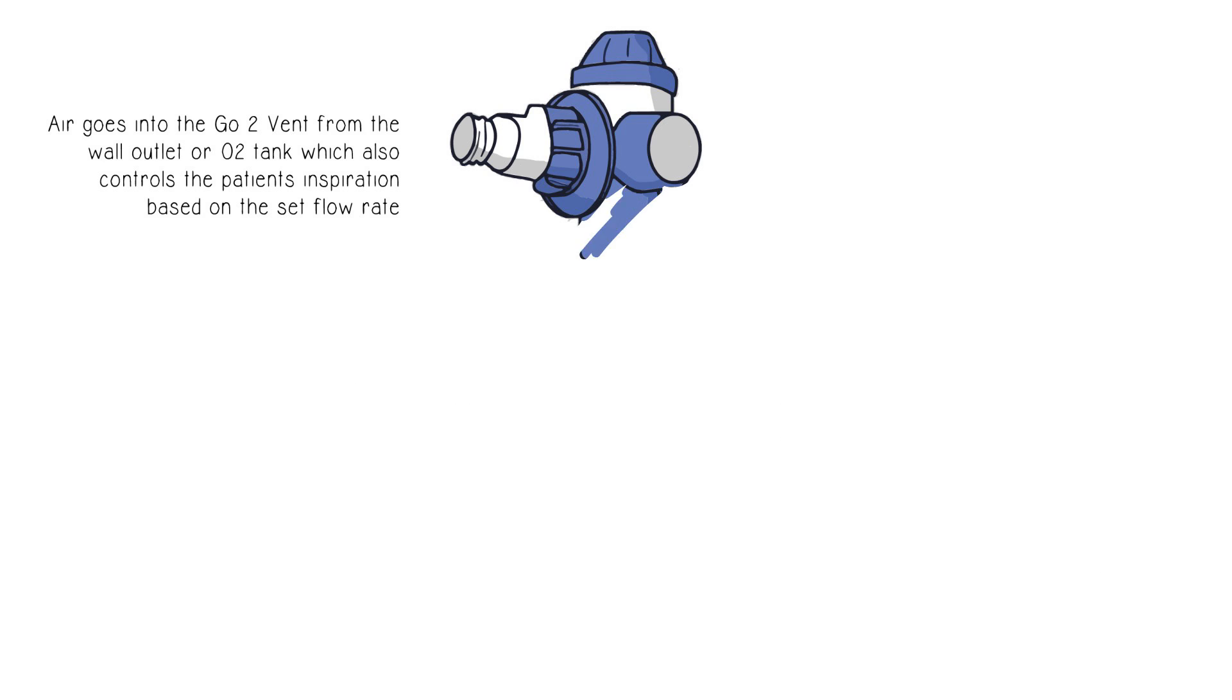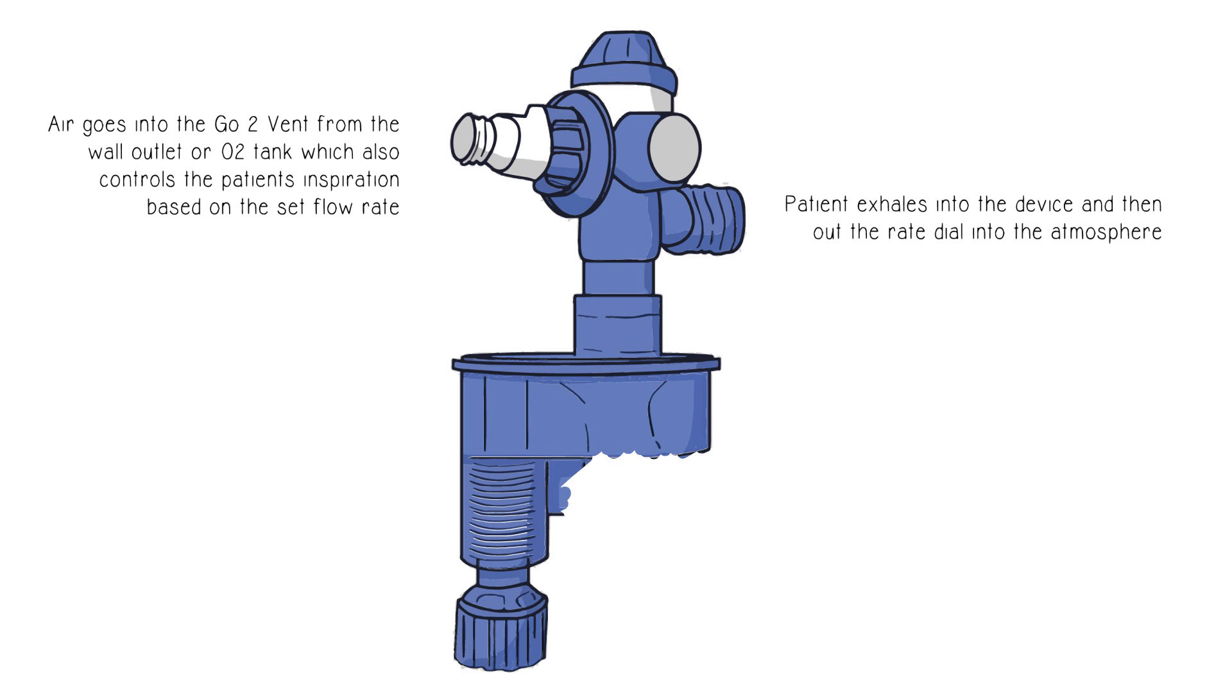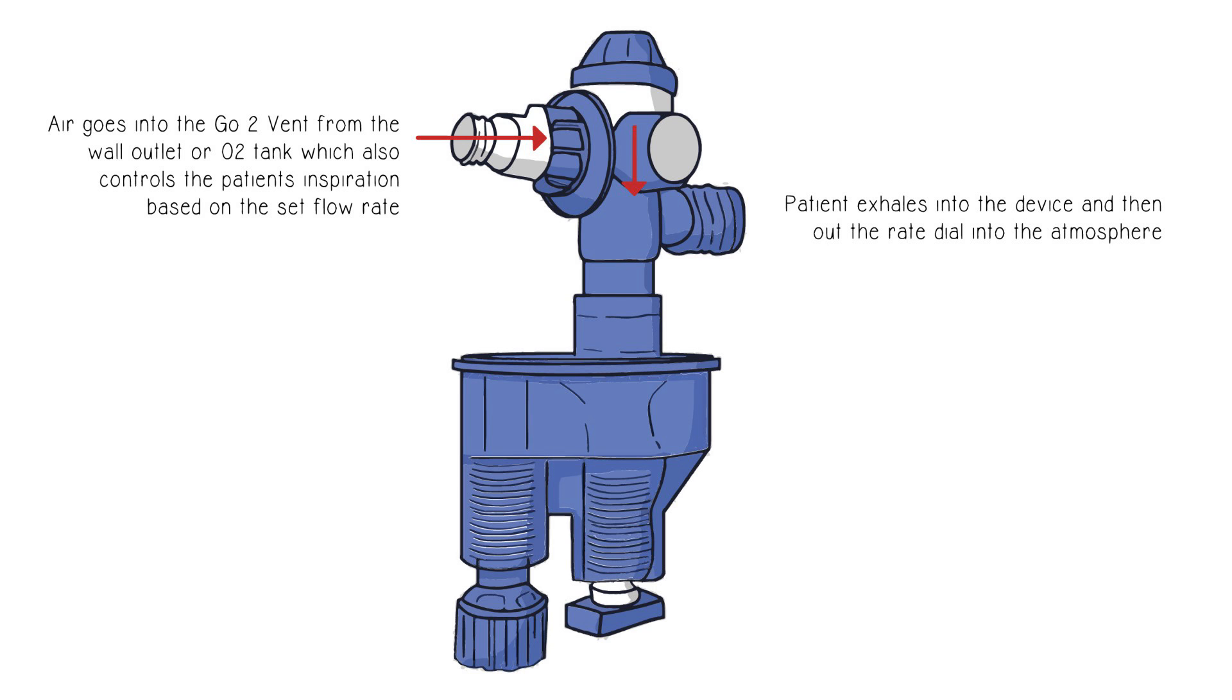Go 2 Vent is gas operated using O2 or air to power the resuscitator and provide consistent hands-free ventilation to your patients without the need for batteries or electricity.